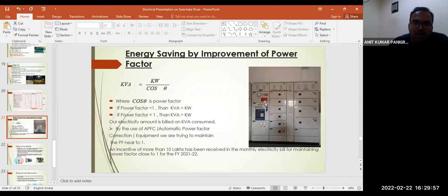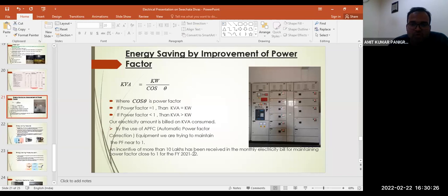So how are we increasing the power factor? You can see on the screen an automatic power factor correction equipment. In every LCS load control station, we have this type of power factor correction equipment. Through this we are achieving a power factor nearly 1, not exactly 1, but near to 1. And if you take the data of financial year 2021-22, we got an incentive of more than 10 lakhs by maintaining the power factor closely equal to 1.